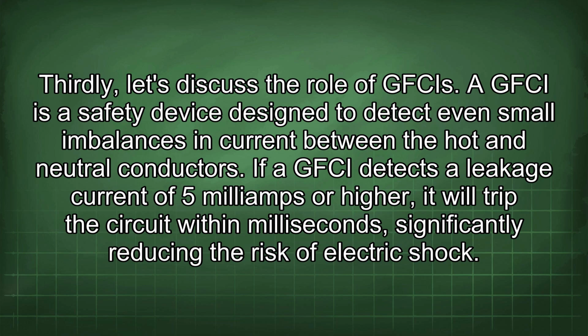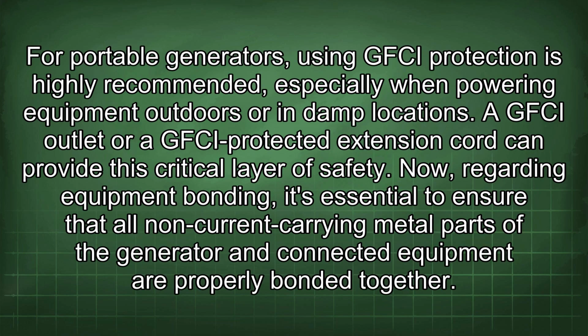A GFCI is a safety device designed to detect even small imbalances in current between the hot and neutral conductors. If a GFCI detects a leakage current of 5 mA or higher, it will trip the circuit within milliseconds, significantly reducing the risk of electric shock. For portable generators, using GFCI protection is highly recommended, especially when powering equipment outdoors or in damp locations. A GFCI outlet or a GFCI protected extension cord can provide this critical layer of safety.